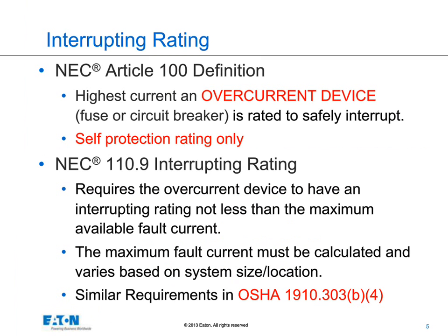NEC 110.9 requires the interrupting rating of the overcurrent device to be adequate — equal to or greater than the maximum available fault current. To determine the maximum available fault current, you would have to do a calculation based upon the size of your system and where you're located in your system. There are similar requirements in OSHA 1910-303-B4. Whether it's a new installation per the NEC or an existing installation per OSHA, we need to make sure our overcurrent devices have adequate interrupting rating so we don't have a potentially explosive situation. If they experience fault current above their interrupting rating, they can actually explode.